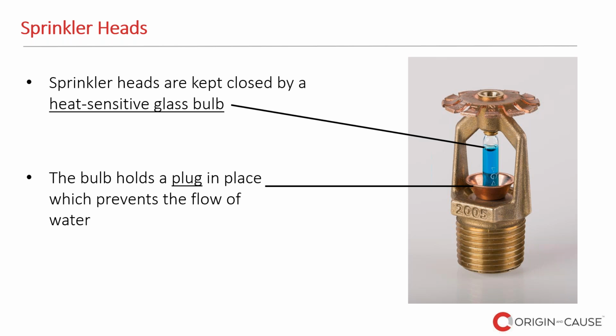So there are a number of cases when some of these sprinkler heads can activate inadvertently or accidentally by either a defect on the glass bulb, or because they've been exposed to heat over a long period of time in the case of the fusible links. But those are very, very rare. It's about 1 in 16 million cases. And most of the times, the activation of the head is a result of something that happened. So either there was heat or there was some interaction from the occupants of that building.